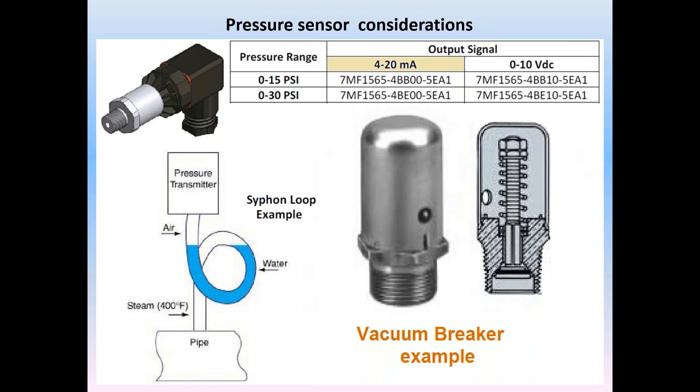If a 4 to 20 pressure sensor is used, and the system cools, oftentimes a vacuum will be created. The pressure sensor will respond with a below 4 milliamp signal. While no permanent damage is caused to the sensor, a lockout will occur until the vacuum is relieved. The use of a vacuum breaker is recommended, or simply use the 0 to 10 volt sensor.